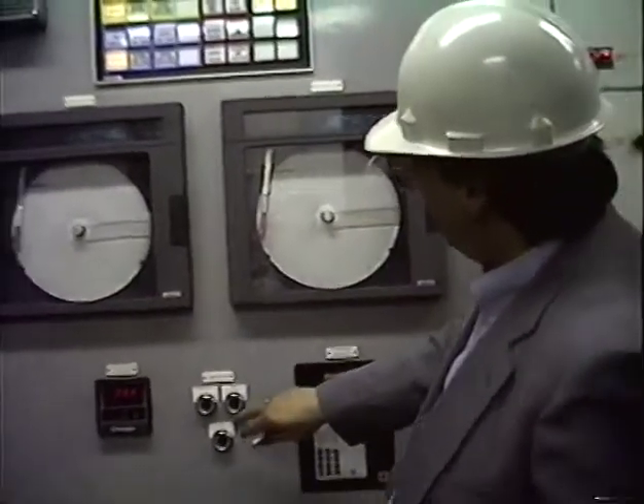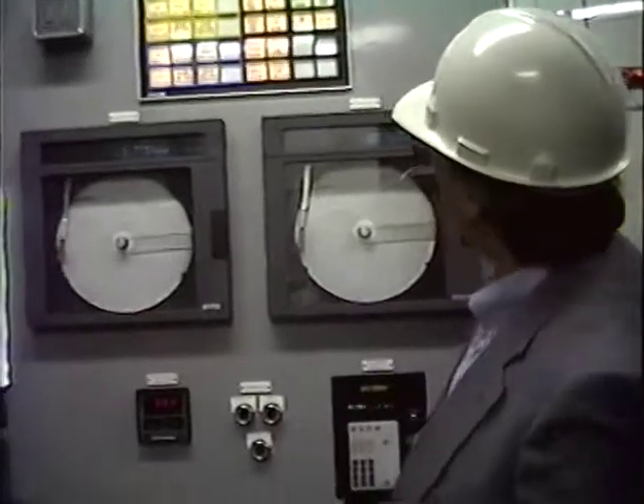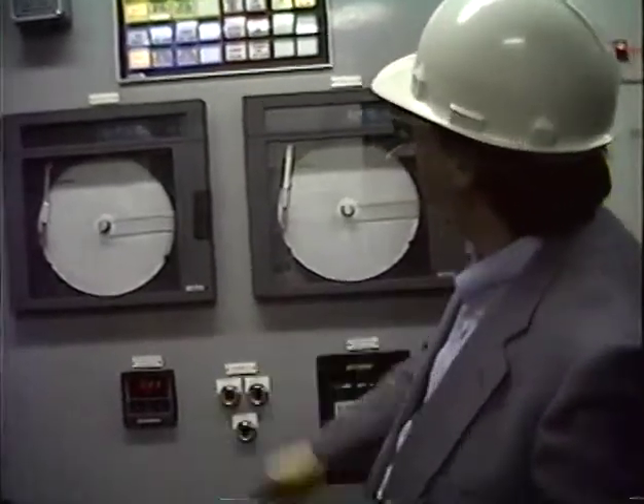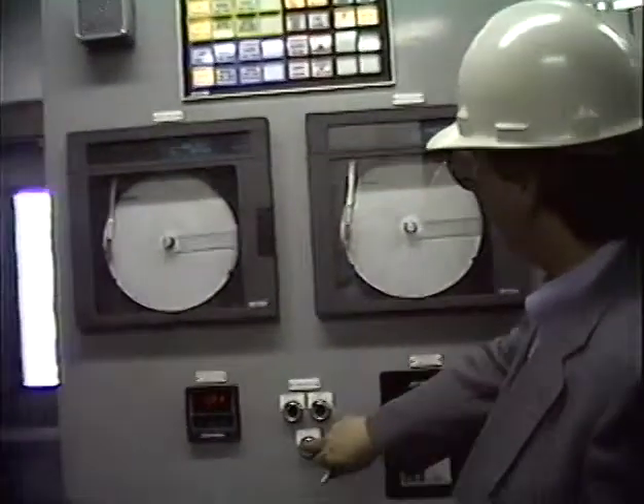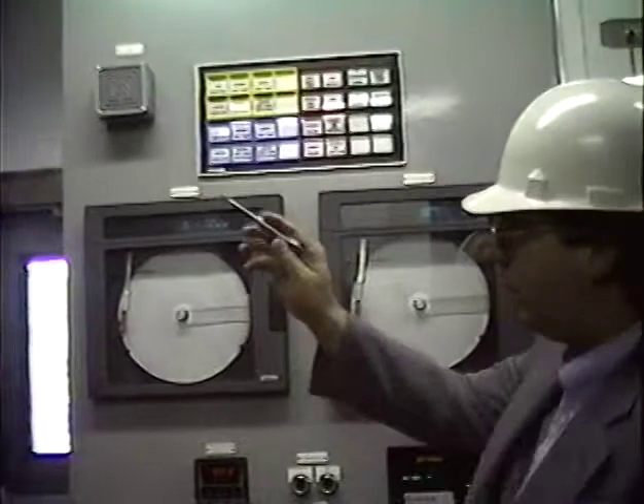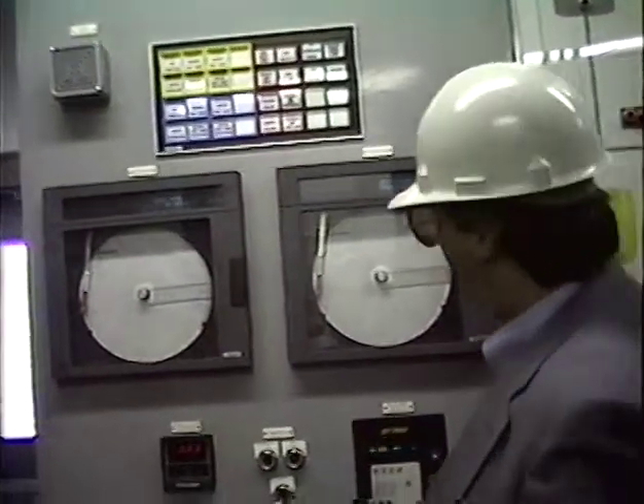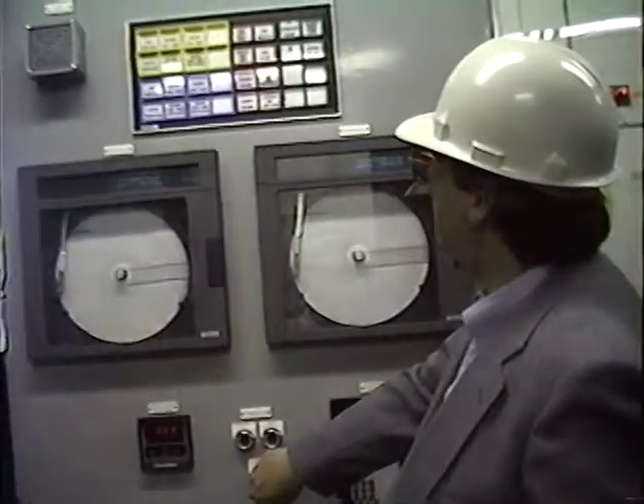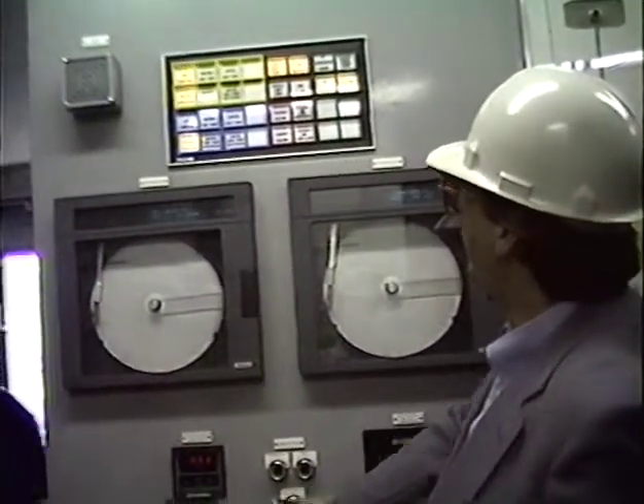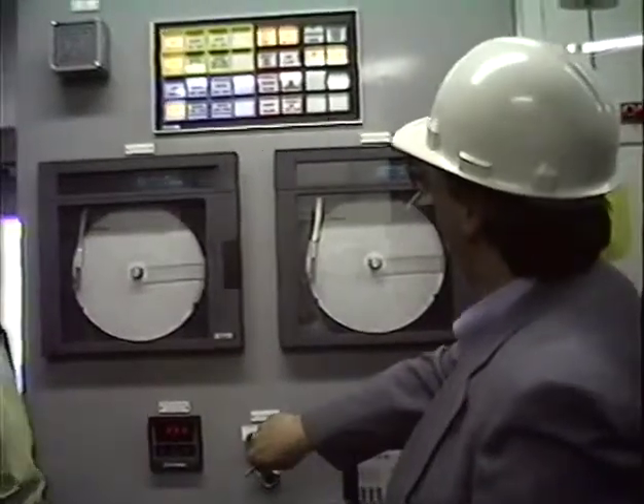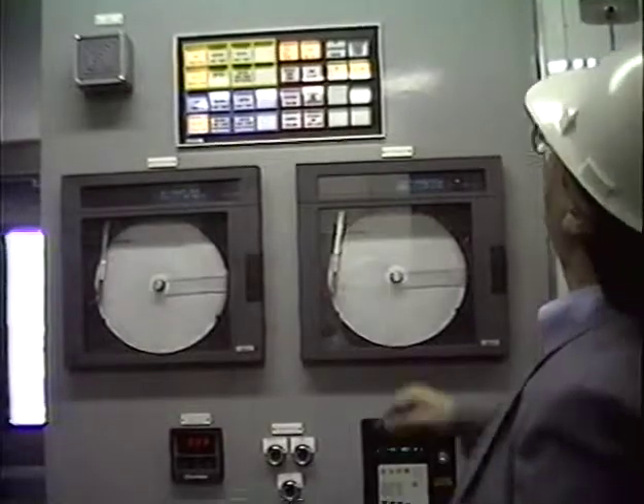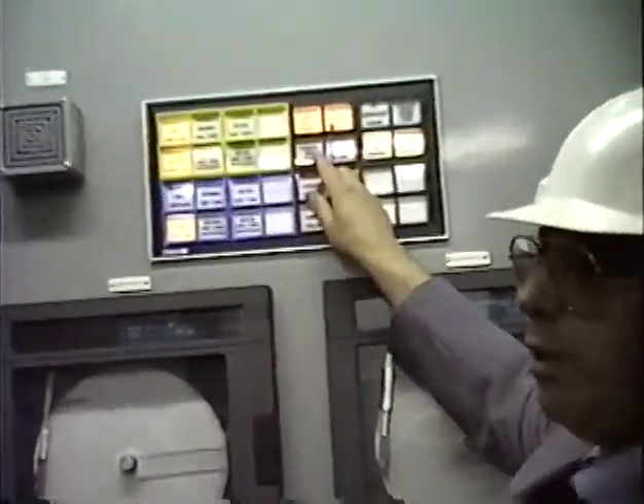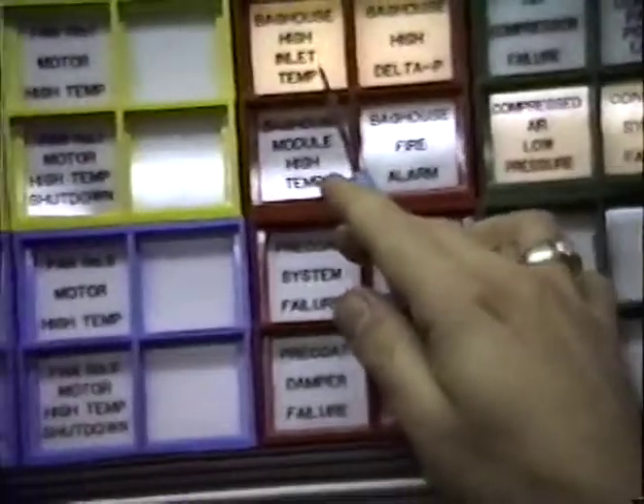Okay, as we talked about, if you've got flashing alarms and you acknowledge them, the ones that are in effect go solid, and if you clear them, they go out. We have a relay interface there with the fan. Hold that button in for 5 seconds, they come back. They come back in a flashing mode. You acknowledge and they go solid. These two are lit because we have normally open instead of normally closed contacts, or vice versa. When we hook up the workstation to the PLC, we'll change those contacts and take care of those. This will go out when the compressor is running, and this will go out when we run the screw conveyors.